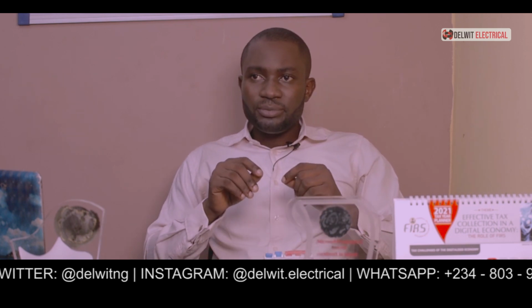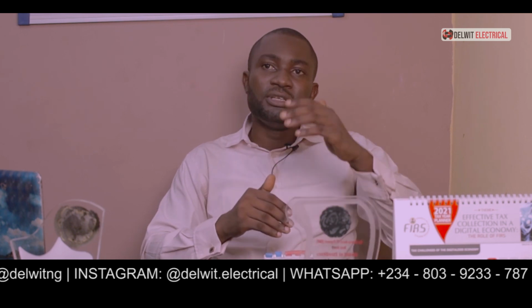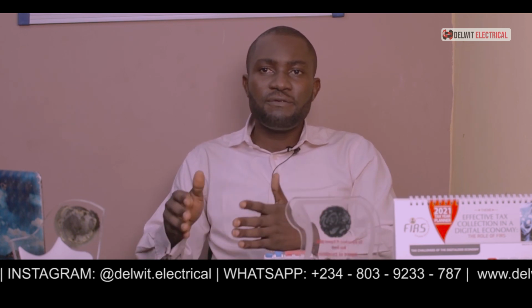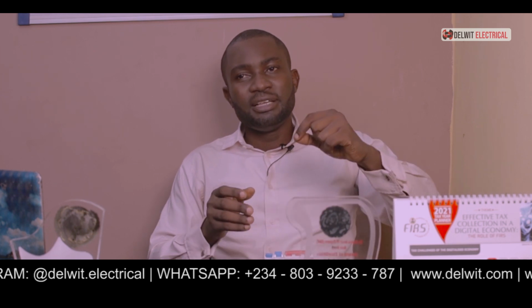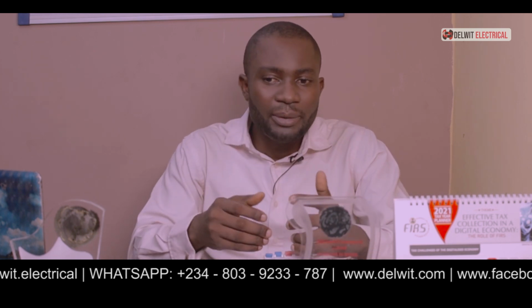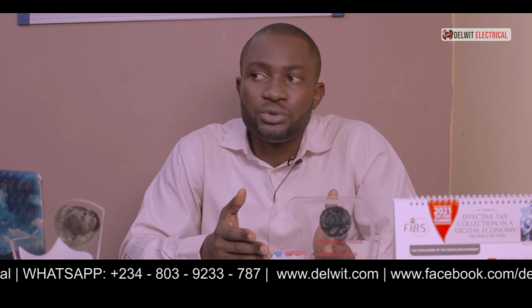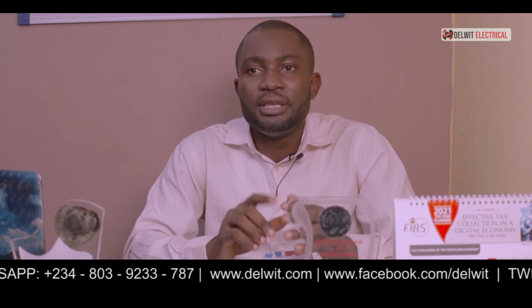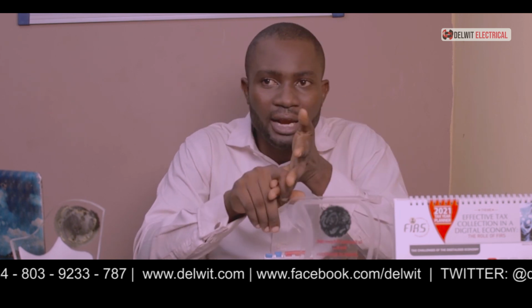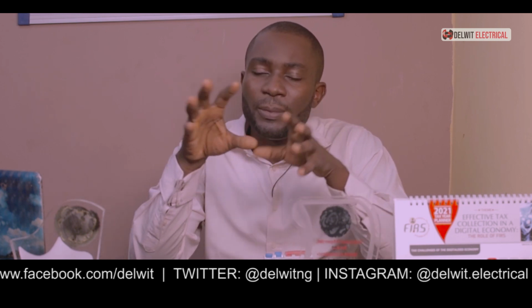The third one we're going to talk about is also similar to short circuit, but that is the ground fault surges. Now, it's similar. For the short circuit, the live and neutral are connected together. But for the ground fault surges, you see that the earth is connected to the live. It can be anything, because your earth is looped in the entire building. So when the live is touching a metal cladding, is touching the surface of your distribution board, the earth wire is touching the live wire in your 13 amp socket, or wherever the live is touching any earthen part of your building, it will lead to this ground fault surge.